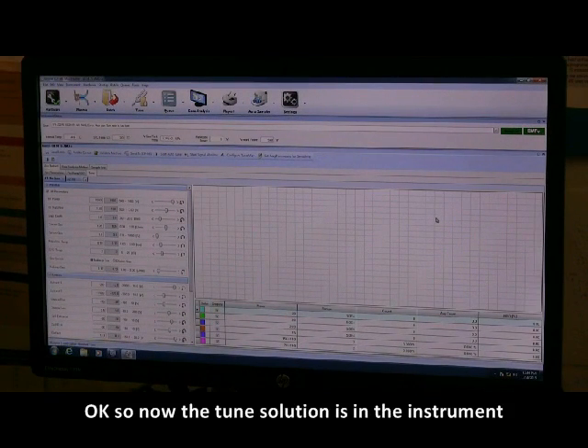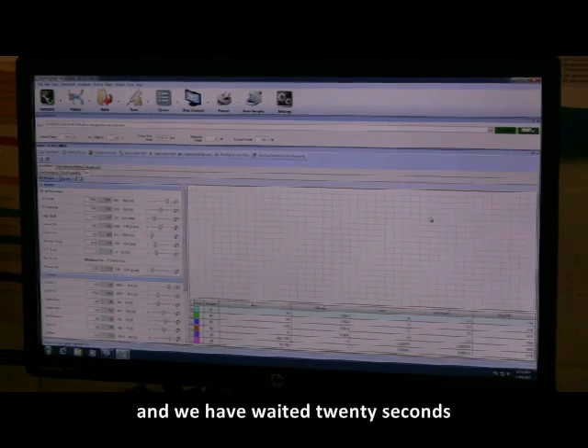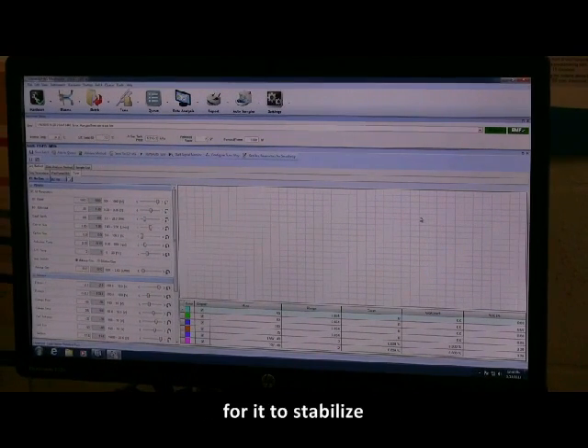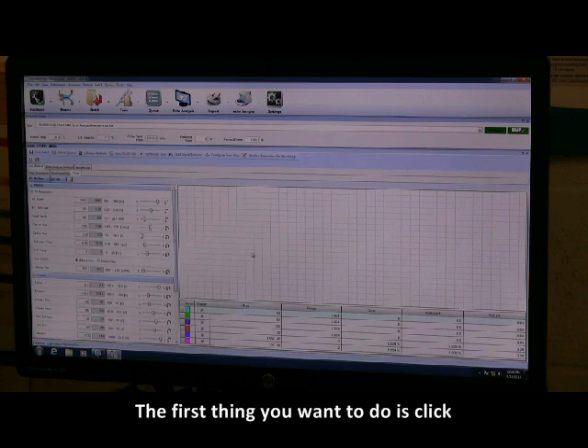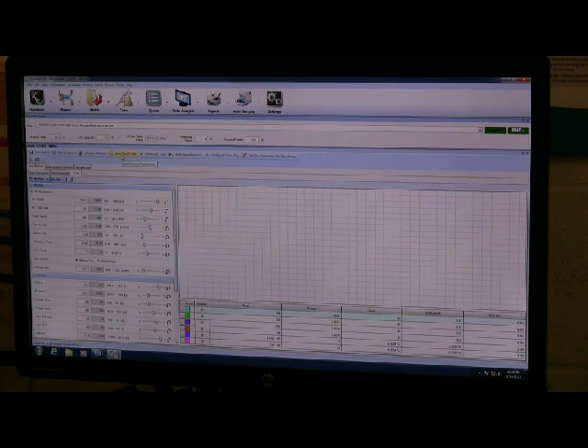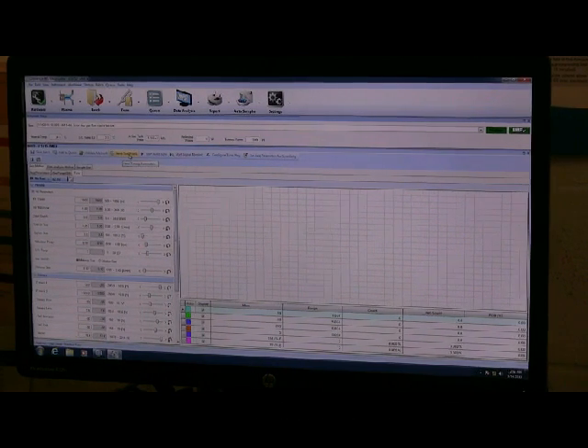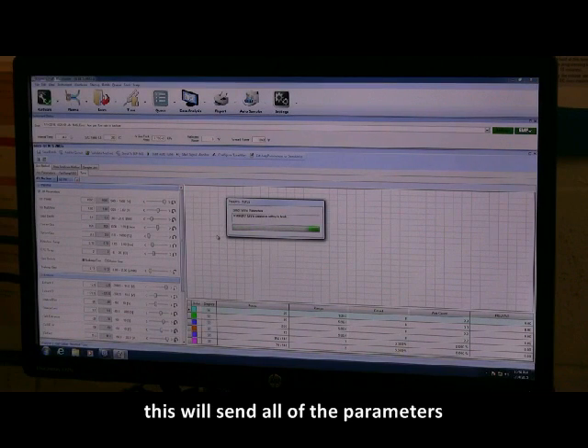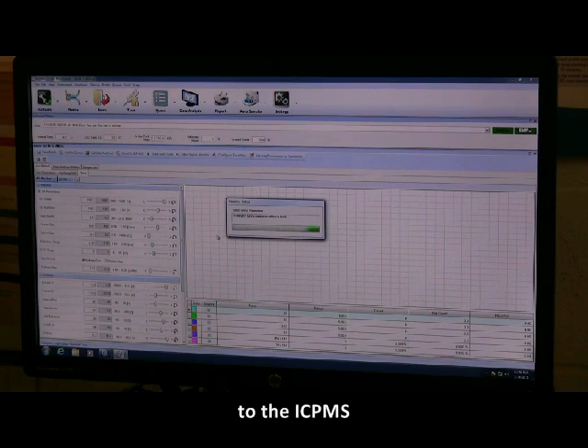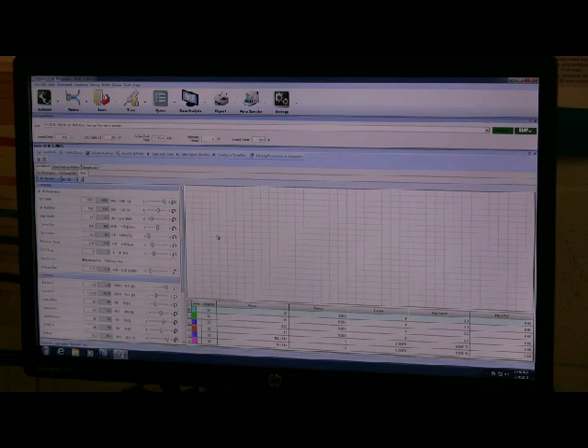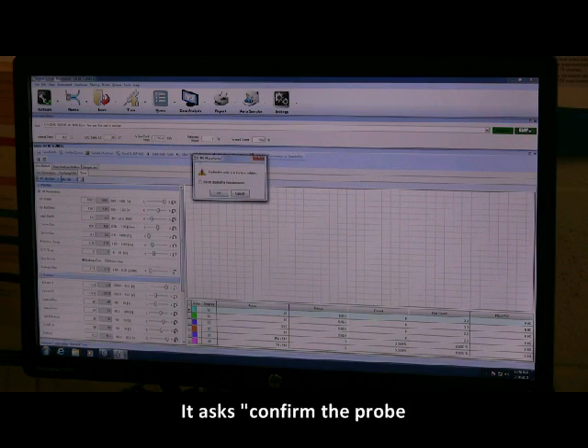Okay, so now the tune solution is in the instrument, and we've waited 20 seconds for it to stabilize. The first thing you want to do is click Send to ICPMS. This will send all of the parameters to the ICPMS. Now you want to click Start Signal Monitoring. It asks, confirm the probe is in the tune solution. Click OK.